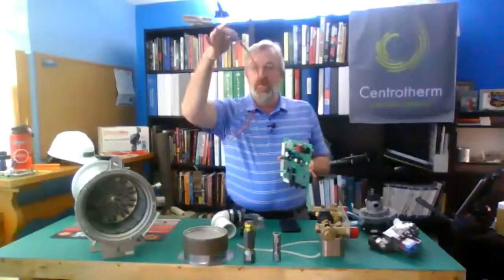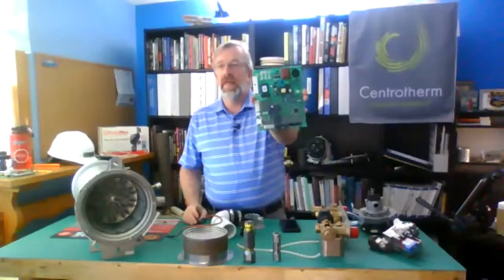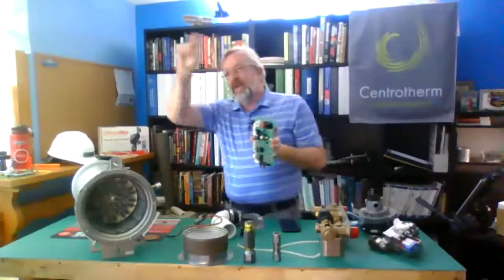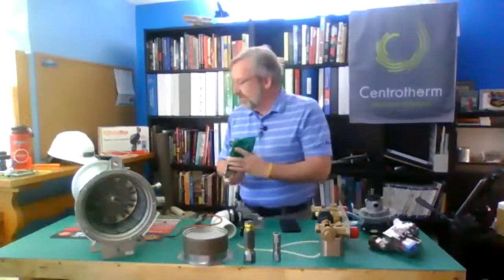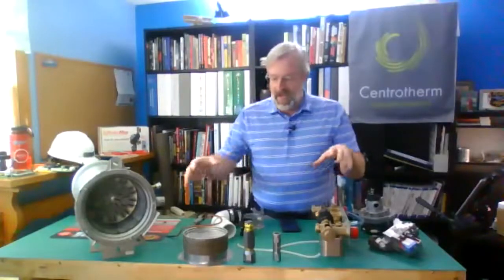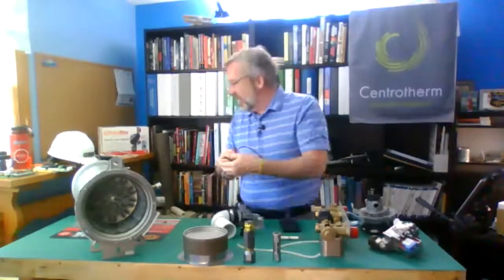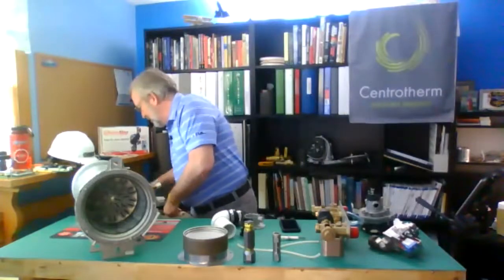It will fire again without you doing anything. So when you do that, your second try will be your igniter. Your third try will be your cable. And your fourth try will be that. And at that point in time, one complete cycle through our ignition before we'd lock out, and I did my gas valve, I did my ignition module, I did my cable, and I did my igniter. Now, we've done that. We're going to pause for a minute, and we're going to kind of evaluate what we got. So if my gas was okay, and my ignition module was okay, but maybe I had some issues here, my next step is actually going to be to check this guy out.